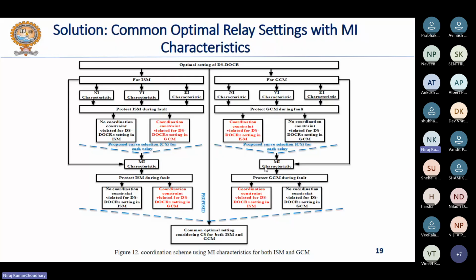So what we have seen is that as the relay characteristics change from normal inverse to very inverse and then to extremely inverse characteristics, the time of operation of the relays will change, and ultimately if the time of operation is getting changed, then your fault detection time is getting changed, right? And if the fault detection time changes, then the fault isolation time will increase or decrease, right? So the possible solution again is that you need to calculate the common optimal settings of the relay for both the modes of operation of the microgrid, considering the mixed inverse characteristics. Meaning in the previous slide, in one of the proposed solutions, we discussed that the common optimal setting of the relay should be obtained considering both islanded mode and grid connected mode.